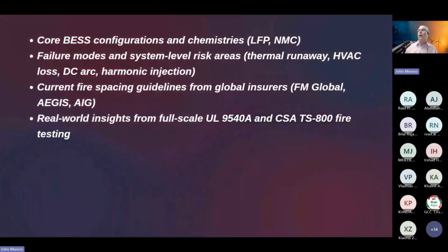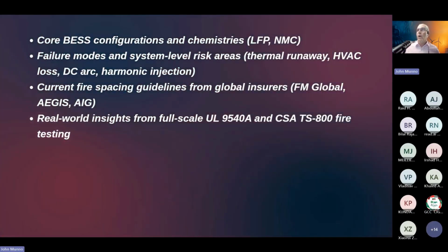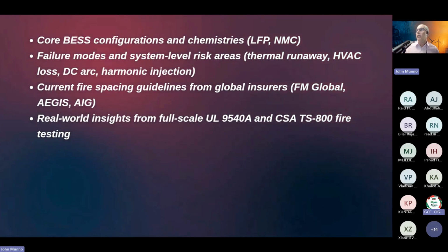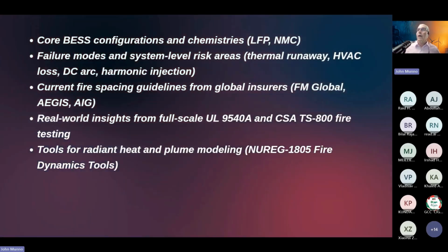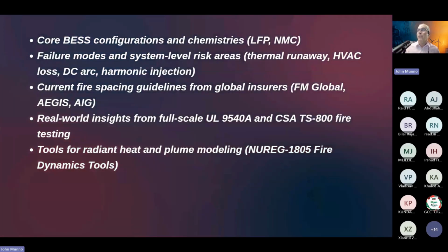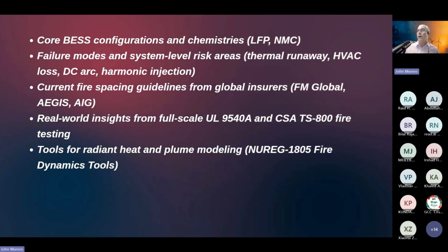And we'll talk about real world insights from full scale UL 9540A and CSA TS-800 fire testing. It's interesting that these tests are required in some cases, so we get a lot of information when we do a real full-scale test. I don't think I've seen this in the past. Even in steam turbines, we rarely could do a full-scale test, but now we're doing them with battery energy storage systems. And I have a set of tools that I want to introduce that's been around for decades, NUREG-1805, which has fire dynamics tools, and we can use those to calculate radiant heat and plume modeling if we have already got a battery system installed and a question comes up, is it safe or not?